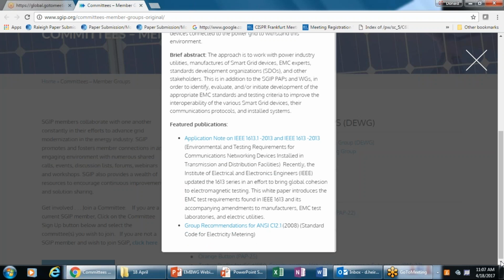But we did one on testing of communication networking, which is probably a more unusual thing that is not necessarily done in box testing for immunity that EMC people do. There you look for performance degradation criteria, acceptance criteria, and it's generally that the device continues to work after the application of a transient of some sort.